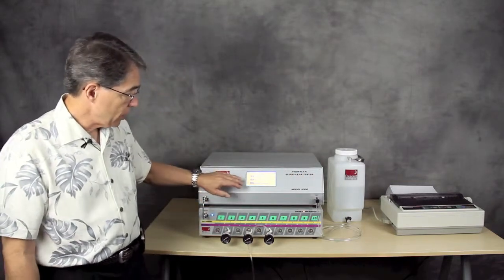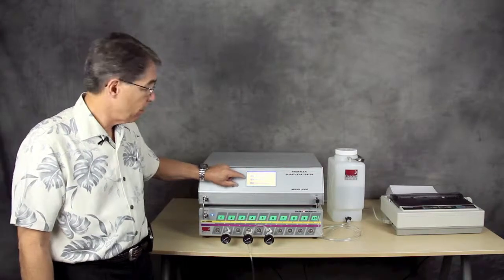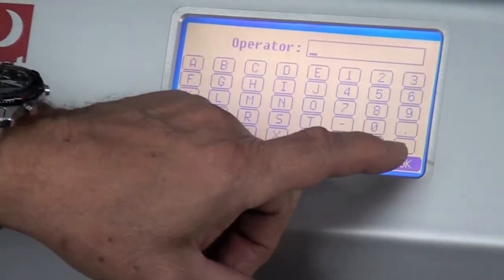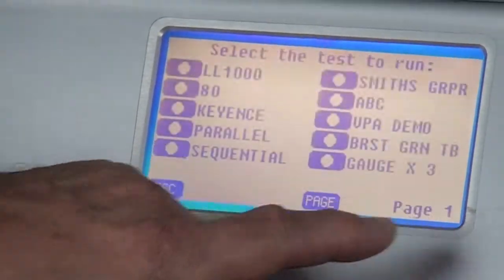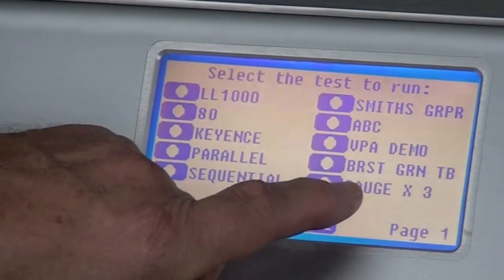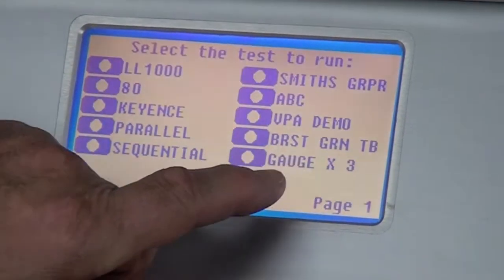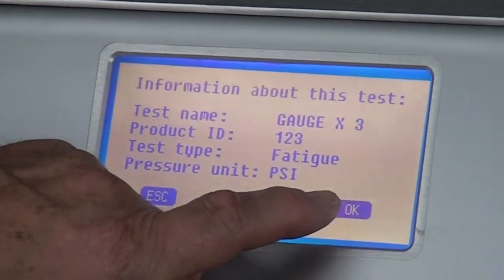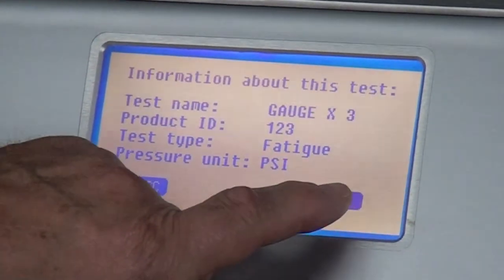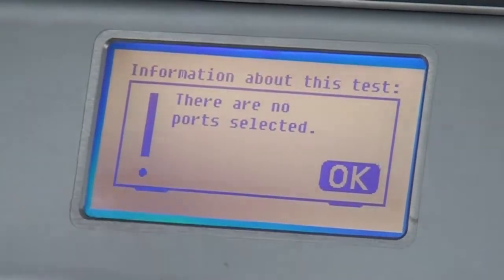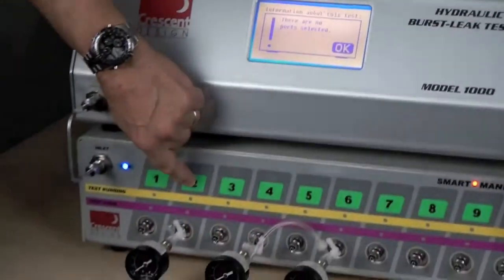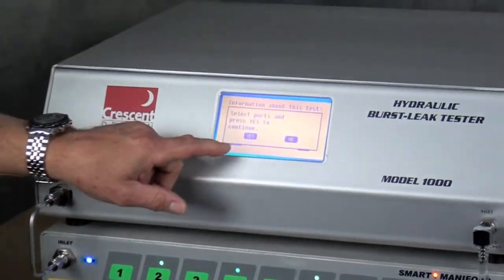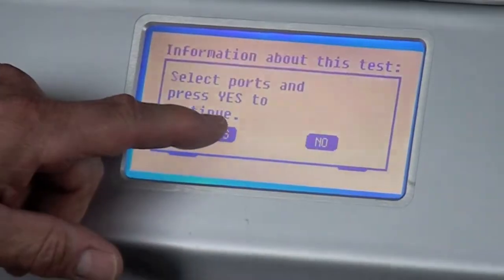So what I've done is I've created a test in the HBLT and we're going to find it here. I'm not going to put an operator or a lot code in right now. And I've created a test called gauge times 3. I'm going to select that. It gives me a brief screen to show me what I've selected. I'm going to say OK. But I didn't select any ports. So let's go ahead and select some ports. In this case 2, 4 and 6. And I have selected them and I'm saying yes.